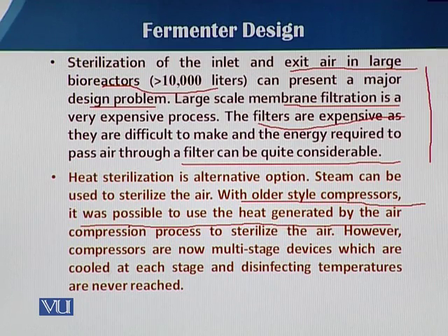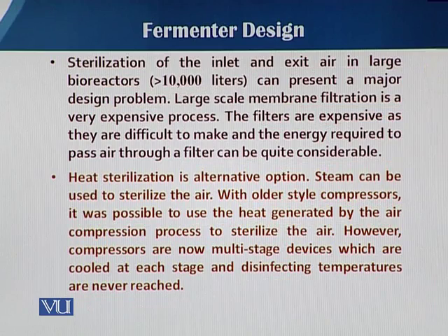But if we use that compressor heat just for the sterilization of the air, then before supply to the fermentation vessel, it has to cool down to the required temperature that is needed inside the fermenter. So before injecting into the fermentation vessel, a cooling system is required that is attached to the fermenter. So that is very critical.